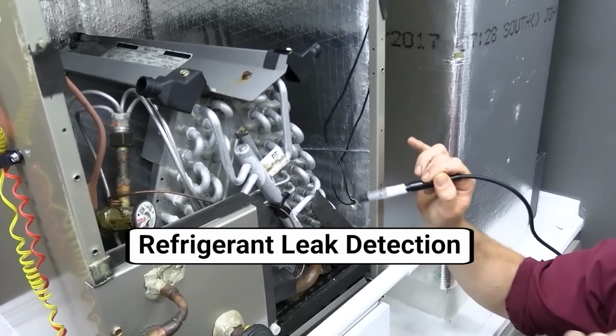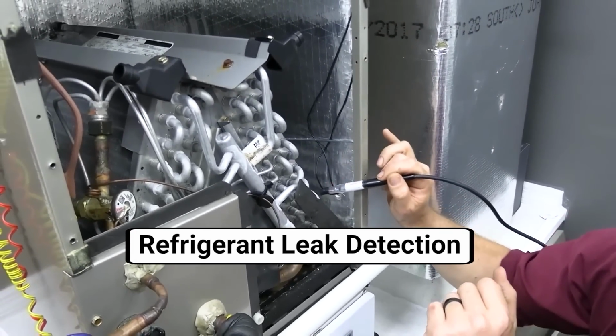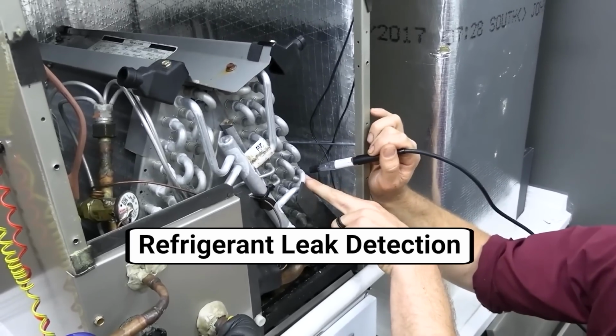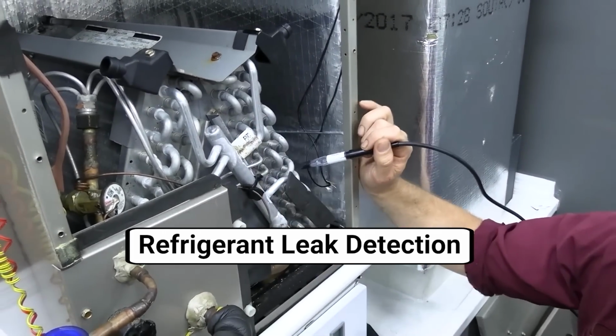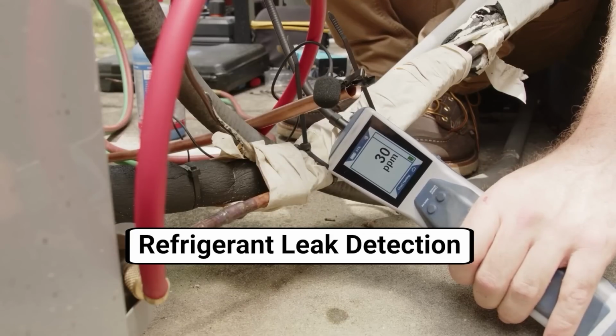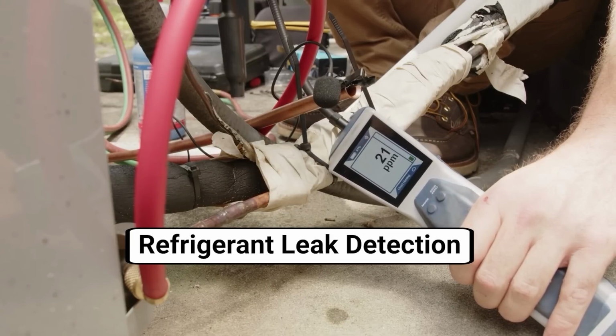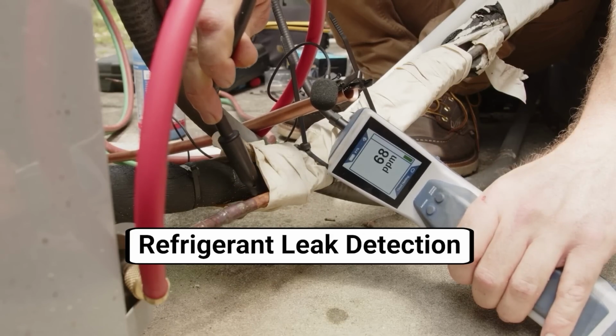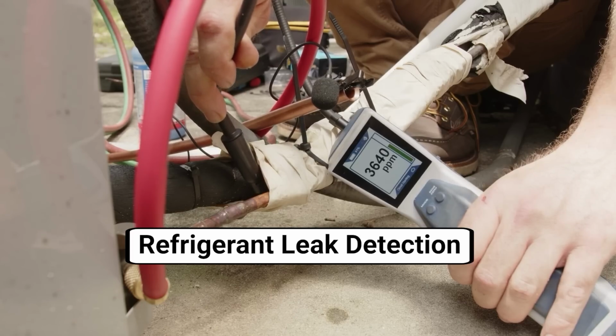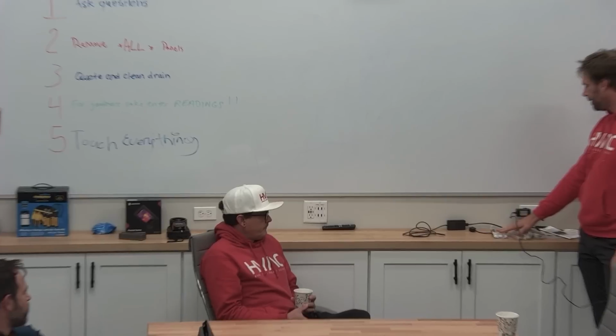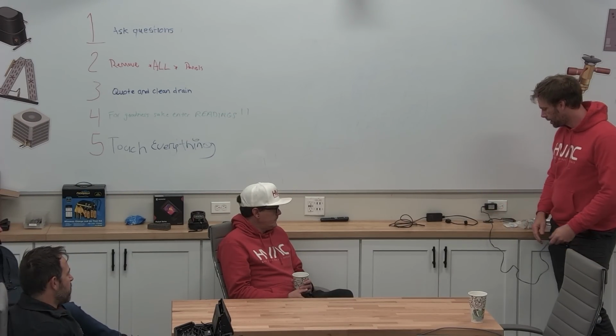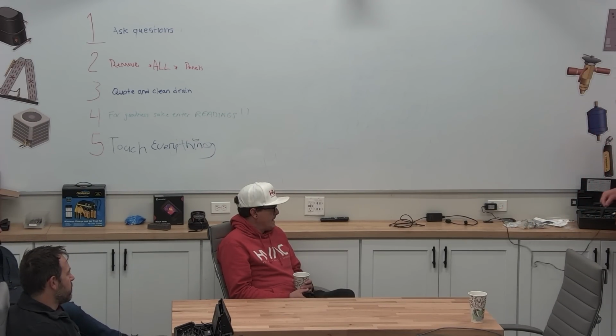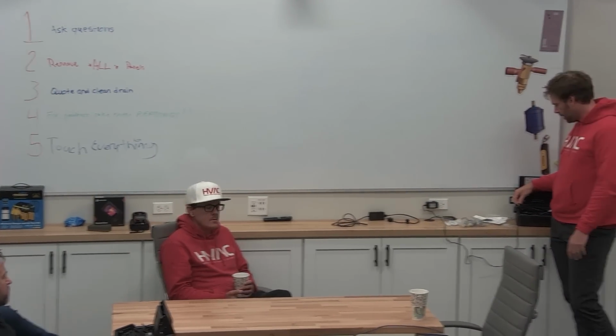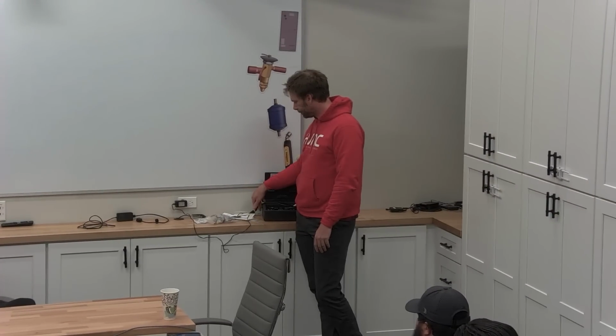Okay, so I still get a lot of conversation about "I need my leak detector checked out. I think there's something wrong. I'm not sure if it's working right." And the longer the leak detection is taking, the more suspicious the leak detector seems. So it's important, for your own sanity and also for finding a leak and not giving out too quick, to be able to trust your leak detector completely.